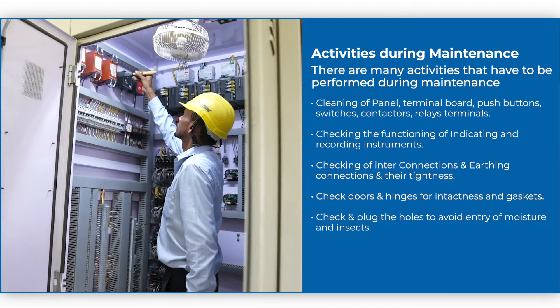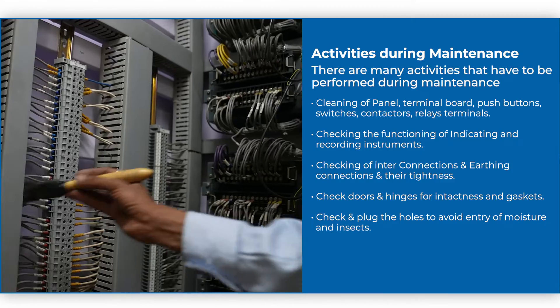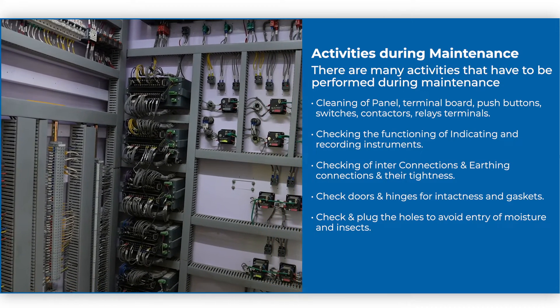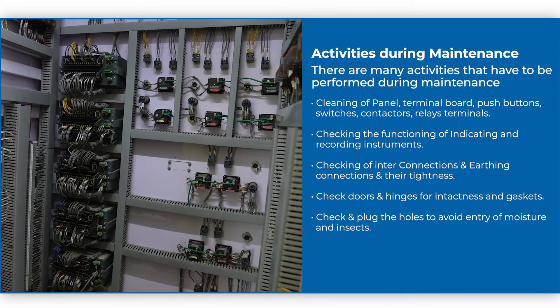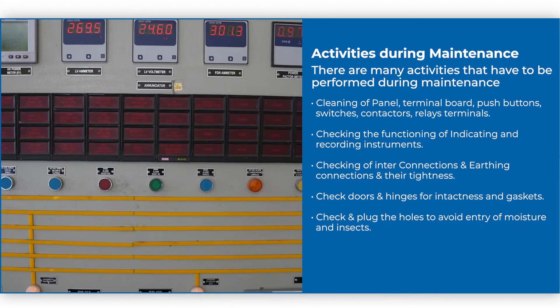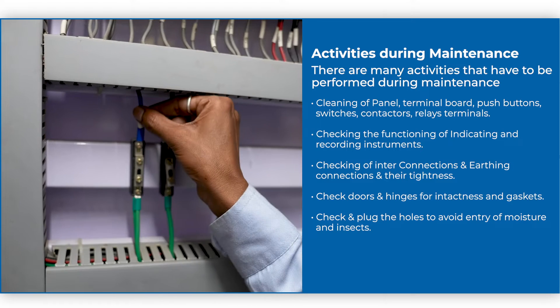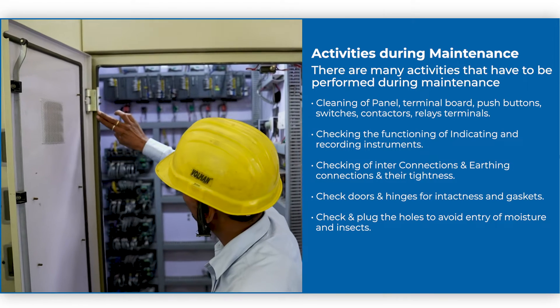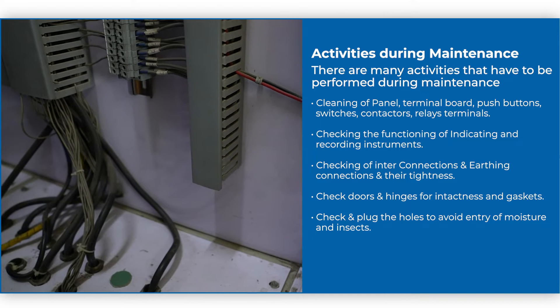There are many activities that have to be performed during maintenance: cleaning of panel, terminal board, push buttons, switches, contactors, relays terminals; checking the functioning of indicating and recording instruments; checking of inter-connections and earthing connections and their tightness; check doors and hinges for intactness and gaskets; and check and plug the holes to avoid entry of moisture and insects.